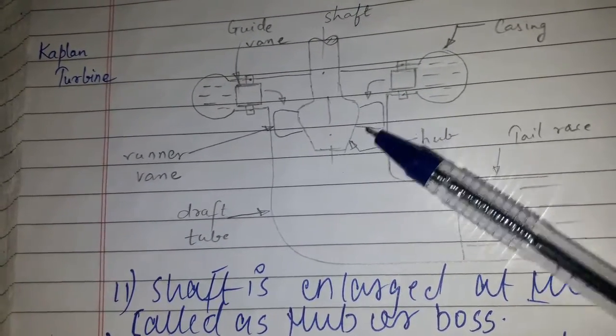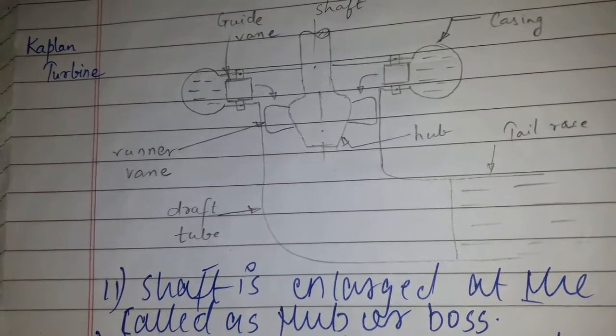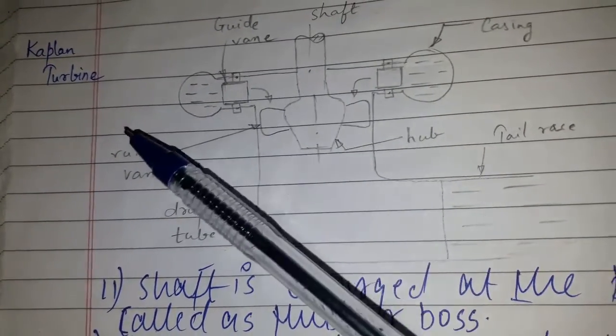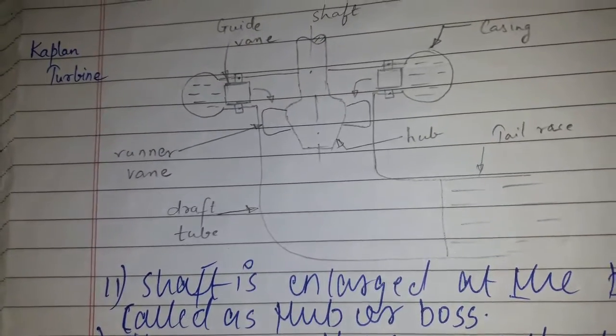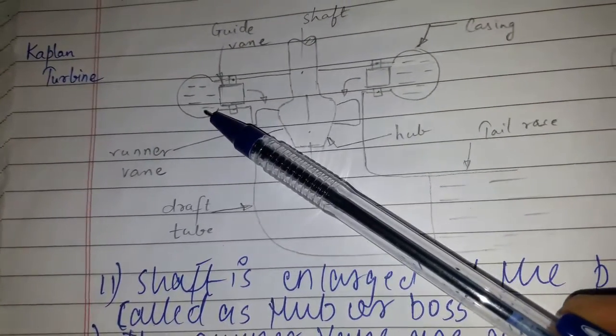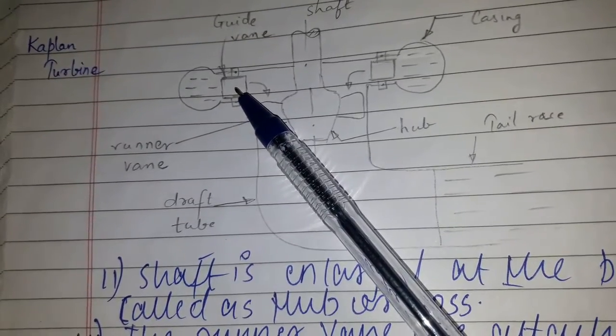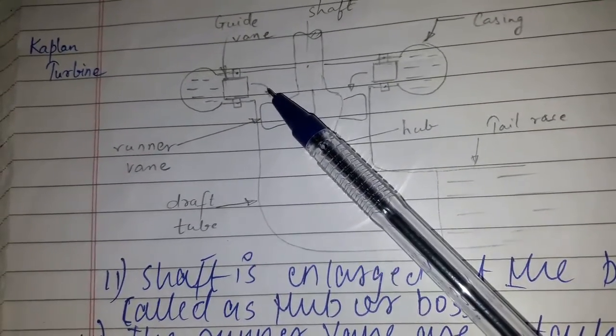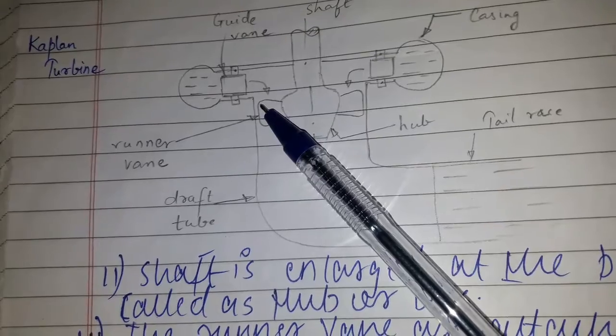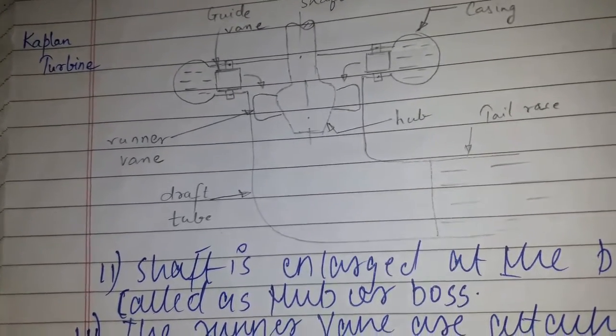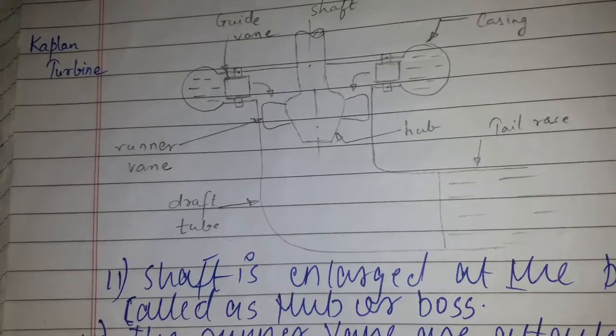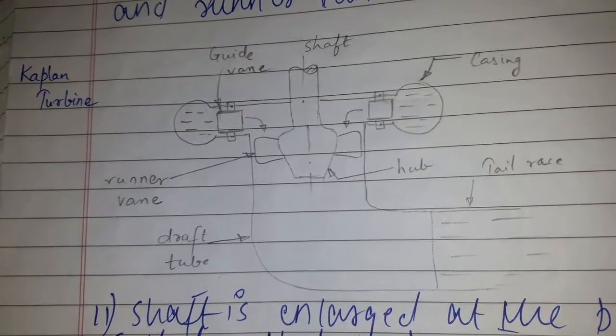Regarding the working of Kaplan turbine, the water from the pen stock enters the casing and into the guide vane. The water from the guide vane turns 90 degrees and enters the runner vane. Kaplan turbine has purely axial flow.